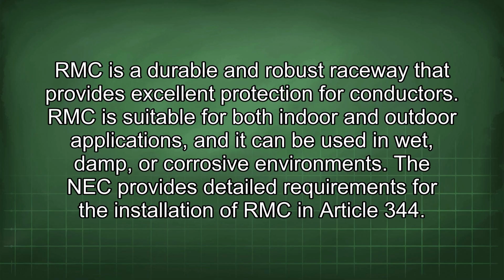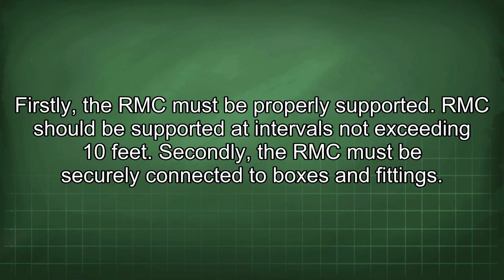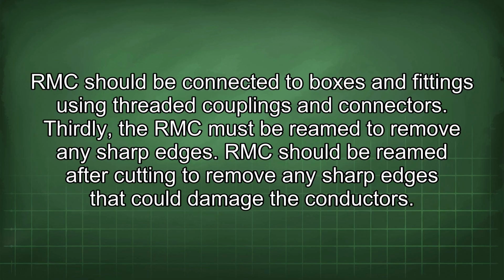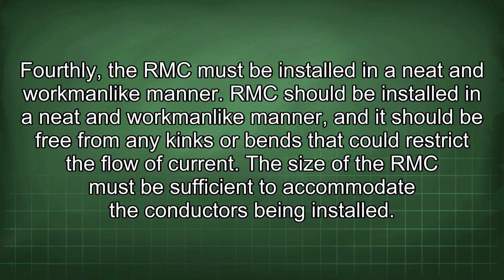Firstly, the RMC must be properly supported. RMC should be supported at intervals not exceeding 10 feet. Secondly, the RMC must be securely connected to boxes and fittings. RMC should be connected to boxes and fittings using threaded couplings and connectors. Thirdly, the RMC must be reamed to remove any sharp edges. RMC should be reamed after cutting to remove any sharp edges that could damage the conductors. Fourthly, the RMC must be installed in a neat and workmanlike manner, and it should be free from any kinks or bends that could restrict the flow of current.